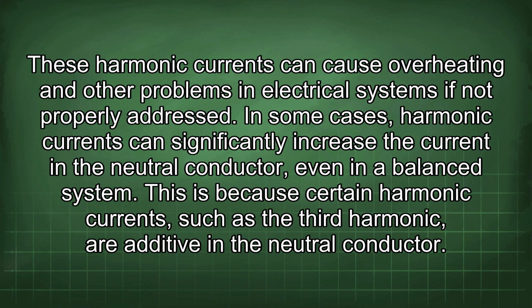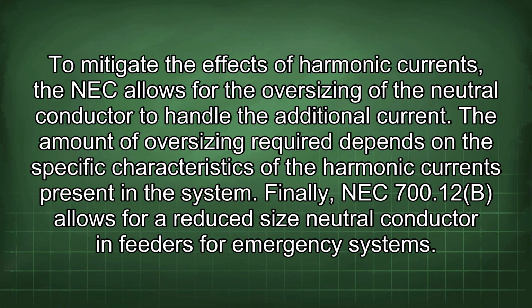In some cases, harmonic currents can significantly increase the current in the neutral conductor even in a balanced system. This is because certain harmonic currents, such as the third harmonic, are additive in the neutral conductor. To mitigate the effects of harmonic currents, the NEC allows for the oversizing of the neutral conductor to handle the additional current. The amount of oversizing required depends on the specific characteristics of the harmonic currents present in the system.